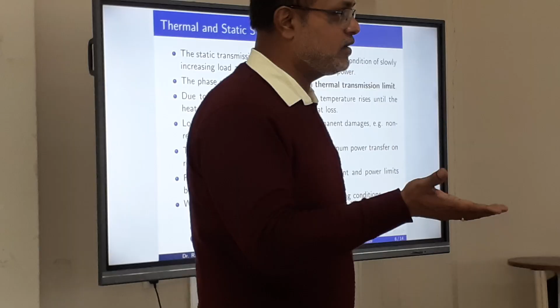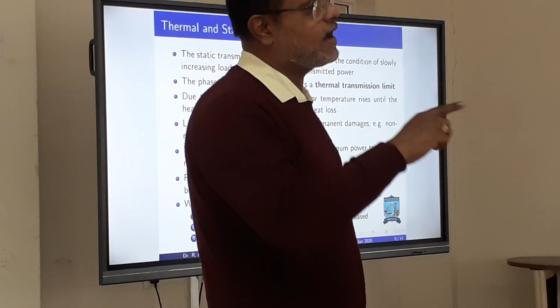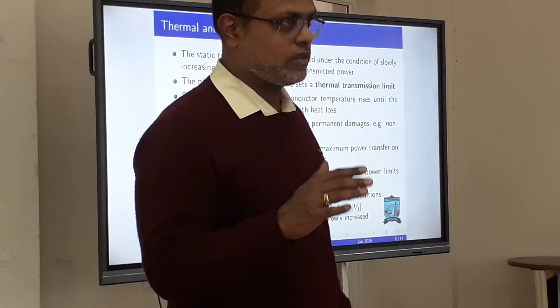Same for the synchronous generator. Whenever a fault occurs, a synchronous generator's power angle goes beyond 90, and we have read in theory that 90 is the maximum limit. Delta equal to 90 is the maximum limit. But a synchronous generator can go beyond 90 during a fault, but only for a fraction of a second. So here we are concerned about only the static stability limit. What is the static stability limit? Delta equals 90 degrees, sin delta equals 1, and for operational purposes we keep it at 30 degrees. In your power angle experiment in the machine lab, the angle you got was not more than 20 or 15 degrees.